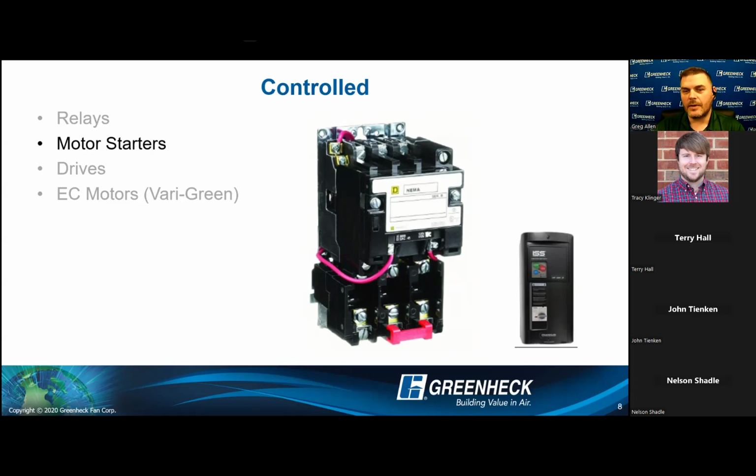Right. And there are some starters that need a specific control voltage to tell it to run. There are other motor starters out there that have both a voltage input as well as a dry input. So if your controlled has two ways of communicating, you're twice the chances of actually having success.